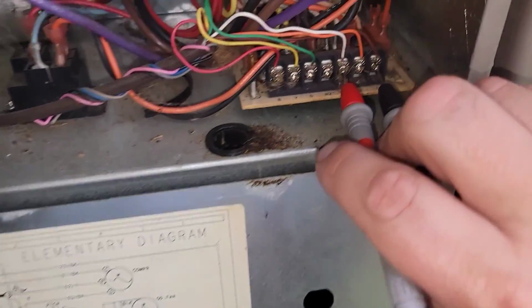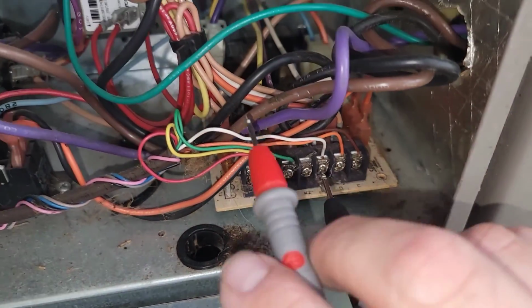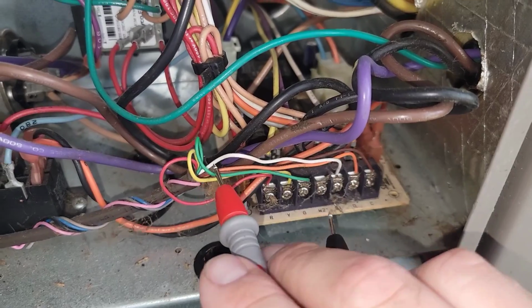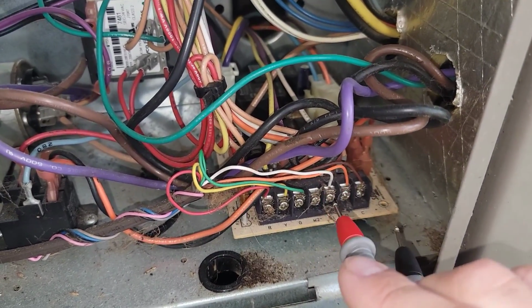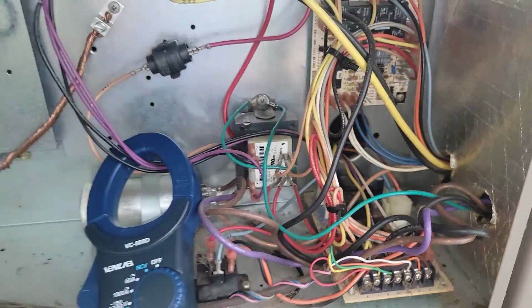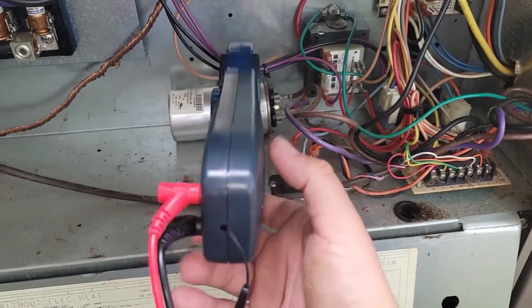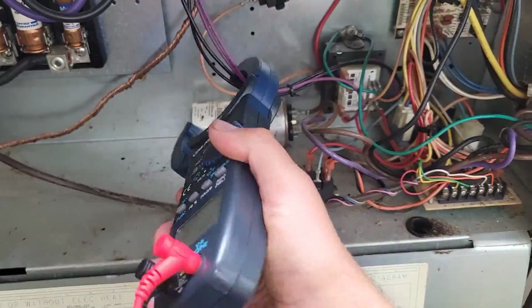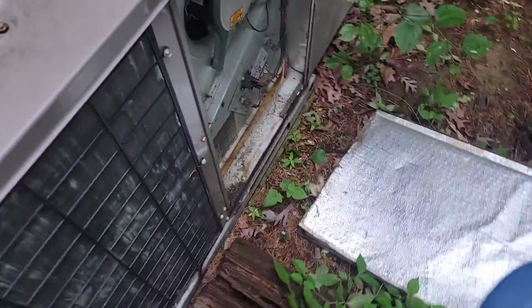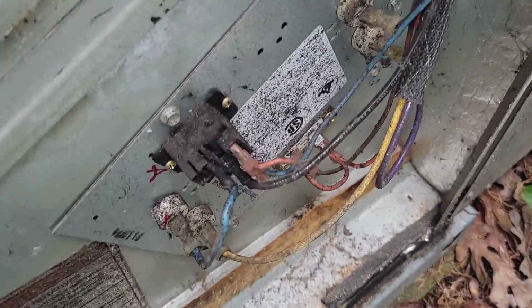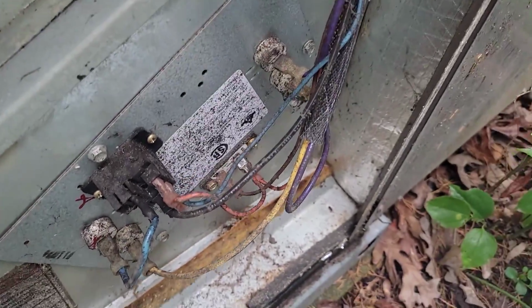Ooh, we got 10 volts. So we could have a shorted stat wire. We could have a bad thermostat that's sending a signal. So what I'm going to do is measure the amp draw of the heater kit and see if we've got one of our heaters pulling. So I've got the panel off over here. Looks like we got 10 kW, we got 2 heaters.